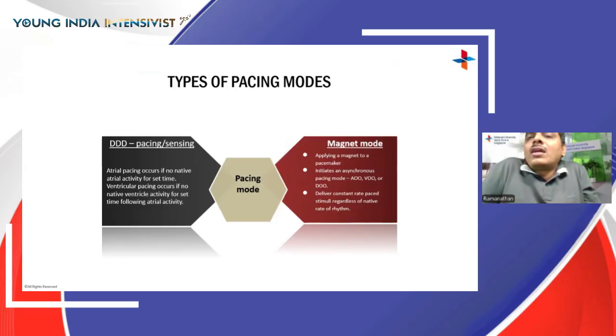Now, one more thing I need to highlight is that all these pacemakers can be modulated by using a magnet. When you apply a magnet to a pacemaker, it goes into an asynchronous mode, irrespective of the initial pacing mode. So there is a magnet mode whereby you would use a magnet to convert any pacemaker into an asynchronous mode, which essentially means that such a pacemaker delivers at a constant rate regardless of the native rate of the rhythm.